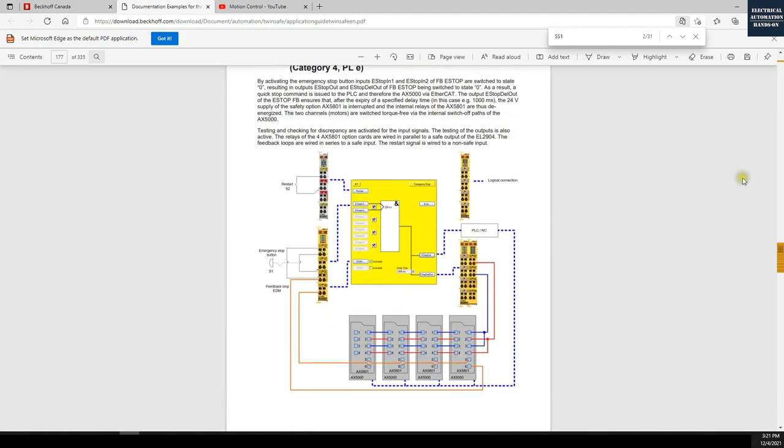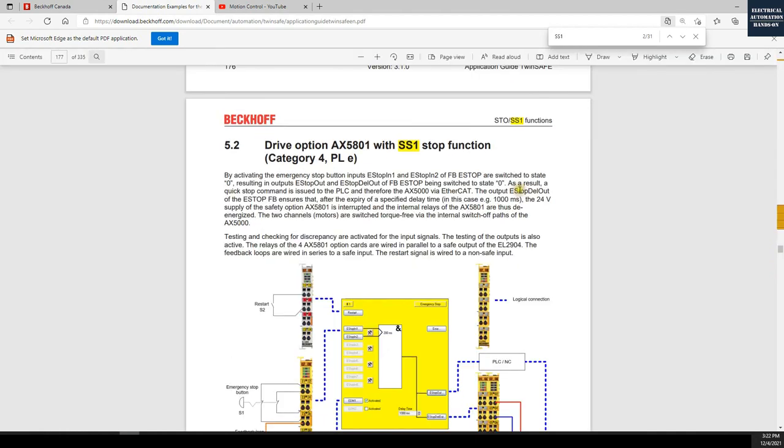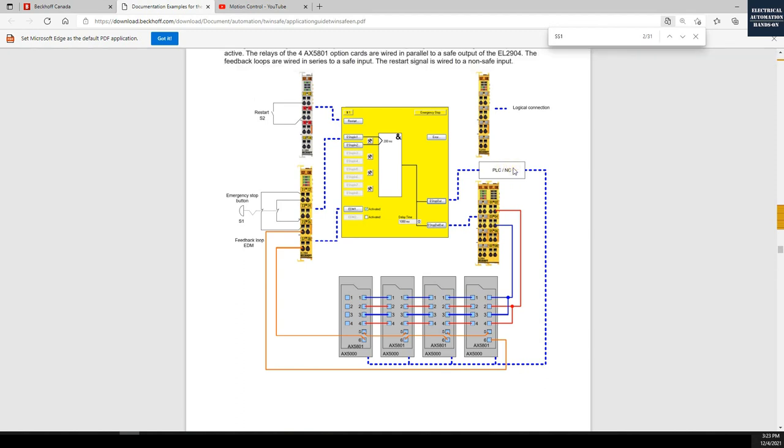From there, search SS1 and you will find one example: drive option AX5801 with SS1 stop function. Click it and you will find a typical example from Beckhoff. This example comes from AX5000, and AX5000 and AX8000 are quite similar. Reading the detail in this paragraph, the key idea to implement SS1 with STO is to use a delay function. When the e-stop function block disables the SS1 signal, the SS1 signal goes to the PLC logic — for example to disable the NC axis.